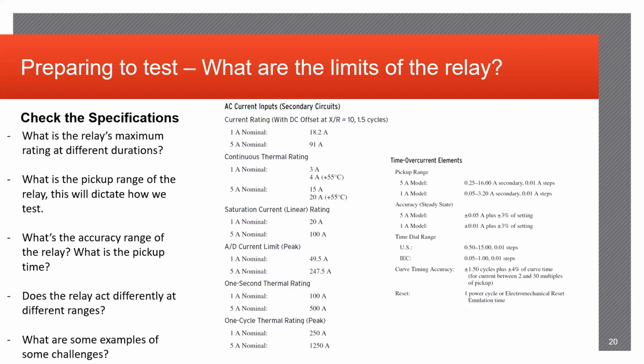So what are the limits of the relay? This is something that you should identify prior to starting any injection values, or even if it's a relay that's completely isolated, even from its DC source, identifying what the DC rating is for the relay. Because as I said before, that battery simulator terminal on your test set can be manipulated anywhere from, I believe, 0 to 250 volts DC. So you want to correctly identify that you're implementing the correct DC voltage to the relay so you don't burn that out.